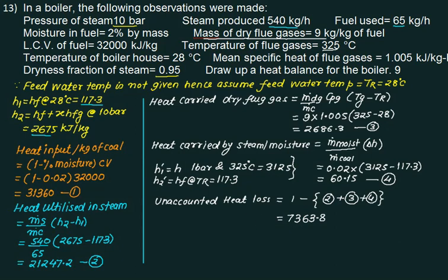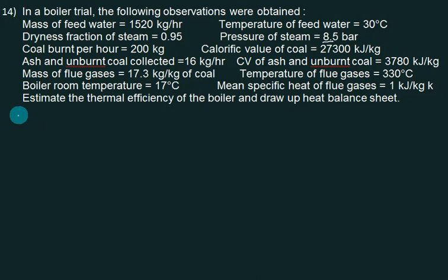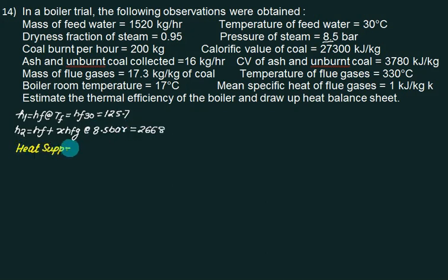Now Problem 14. In a boiler trial, the following observations were obtained: mass of feed water equals 1520 kg/hr, temperature of feed water equals 30°C, dryness fraction of steam equals 0.95, pressure of steam equals 8.5 bar, coal burnt per hour equals 200 kg, calorific value of coal equals 27,300 kJ/kg, ash and unburnt coal collected equals 16 kg/hr, CV of ash and unburnt coal equals 3780 kJ/kg, mass of flue gases equals 17.3 kg/kg of coal, temperature of flue gases equals 330°C, boiler room temperature equals 17°C, mean specific heat of flue gases equals 1 kJ/kg K. Estimate the thermal efficiency of the boiler and draw up heat balance sheet. Write first h1 equals hf at feed water temperature, which is 125.7. What is h2? hf plus x·hfg at pressure 8.5 bar with dryness 0.95, which equals 2668. Heat supply equals 1 minus... moisture is not present but ash is present, so this is percentage of ash multiplied by calorific value of coal.